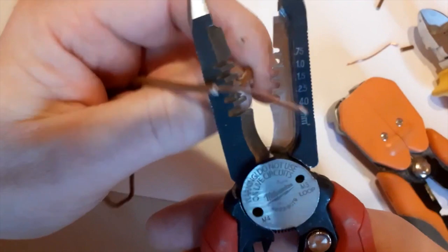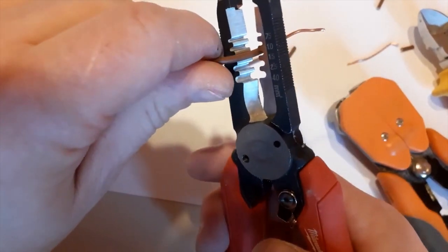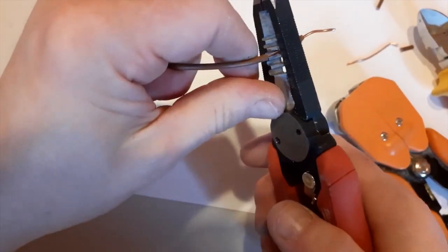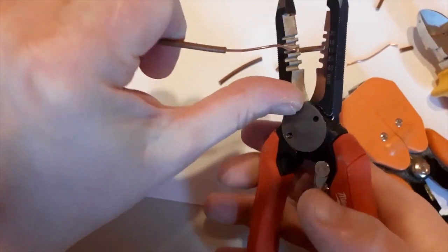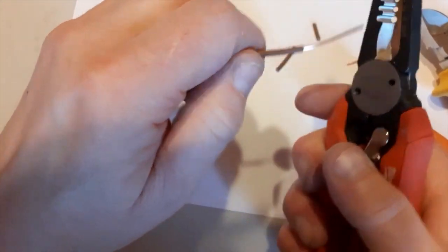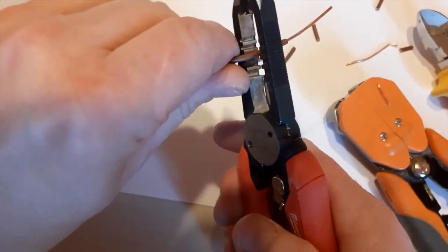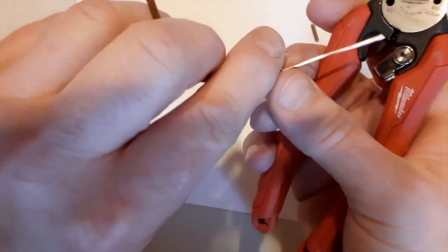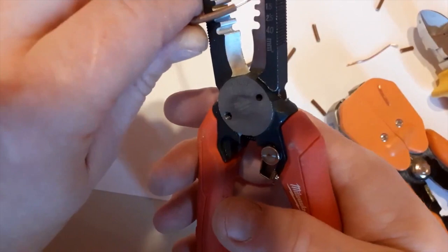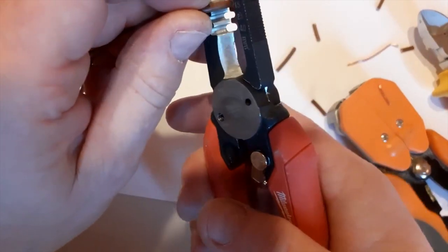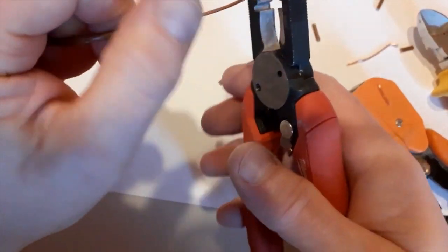I quite like using these really. I think at the end of the day the little notches are in, so you know that you cannot be damaging the conductor. But sometimes these can be tricky to use. You have to make sure you do use the right size hole because if you use a hole that's too small, you're going to damage the conductor. So these do take a bit of getting used to.